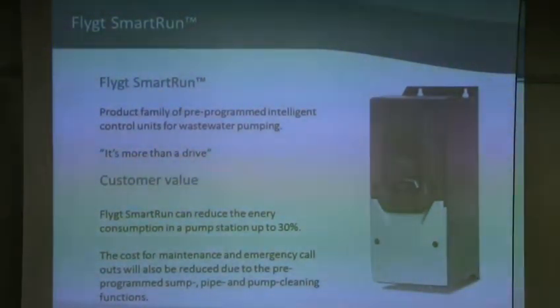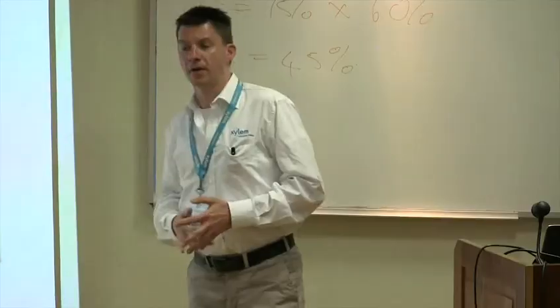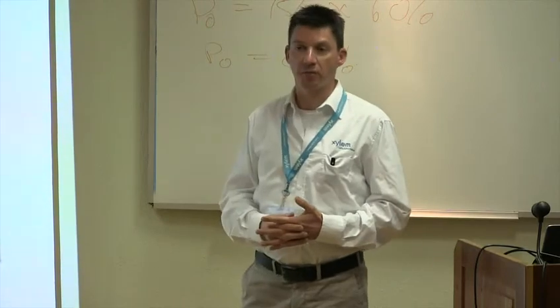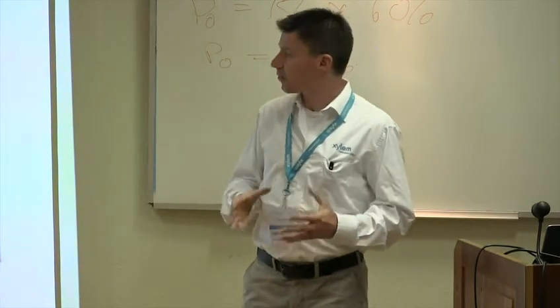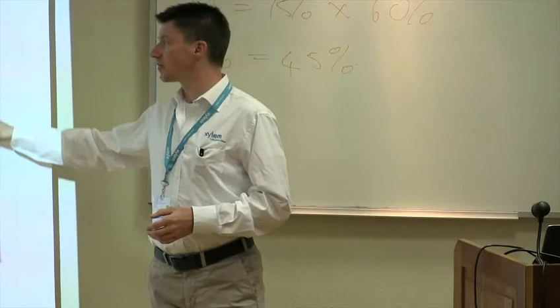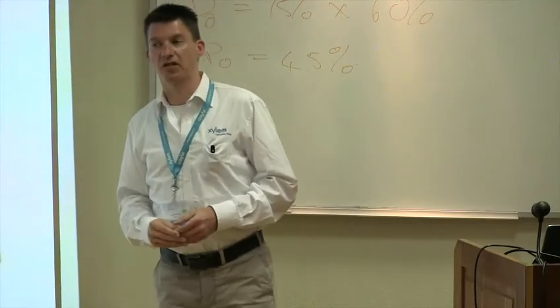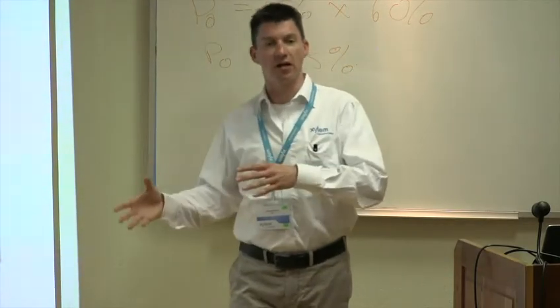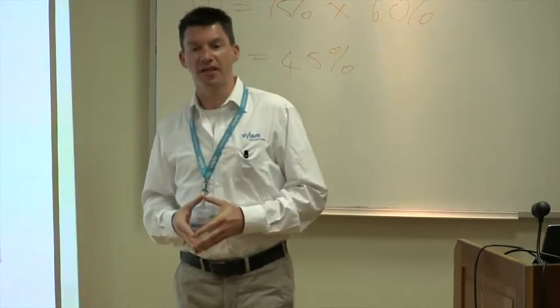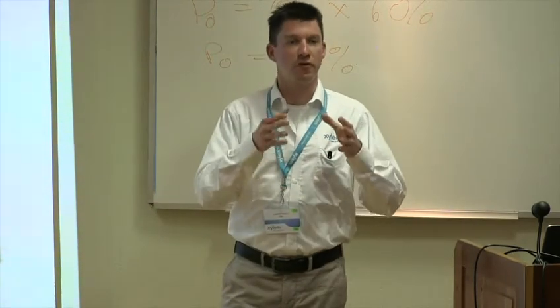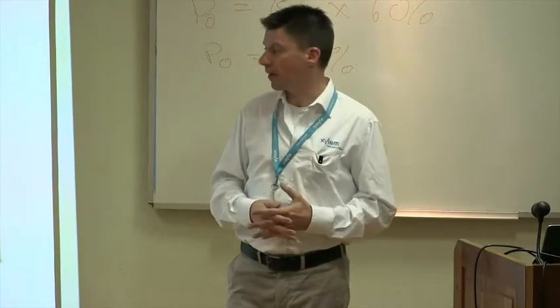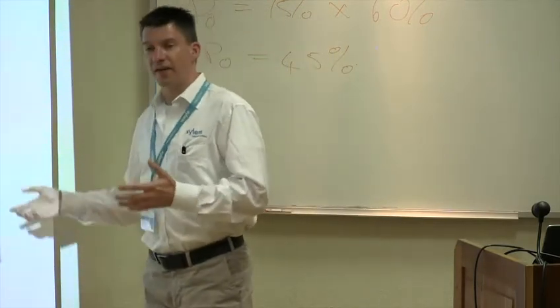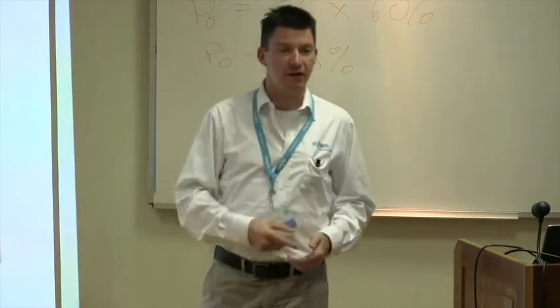One of the two things is the SmartRun - that's our drive, so to say, but actually it's more than a drive. Basically there is a VFD inside from a normal drive supplier, but what we've done, in conjunction with this supplier, is make special software for it. It's not conventional VFD software - this software is tuned for wastewater pumping, for wastewater pump stations, with a lot of cleaning functions inside.